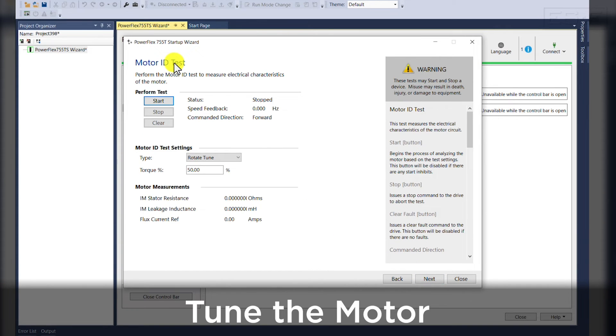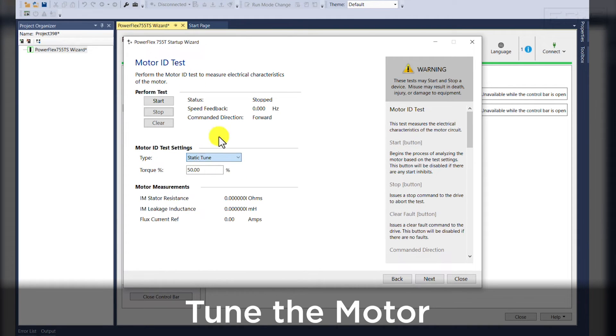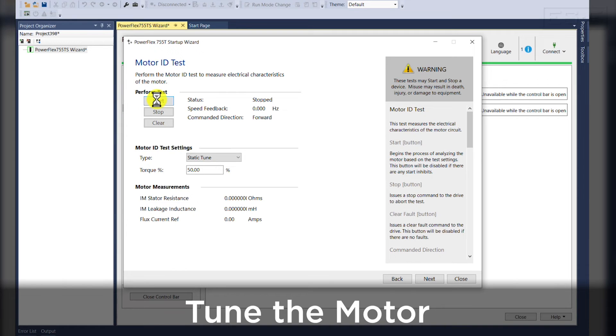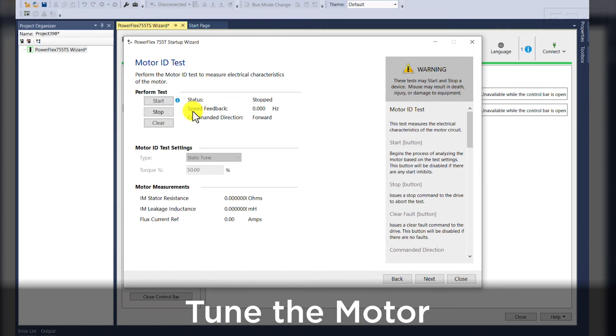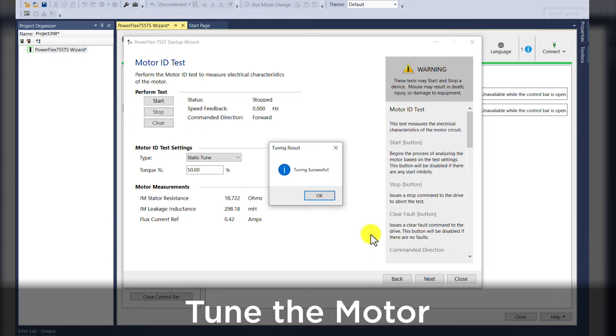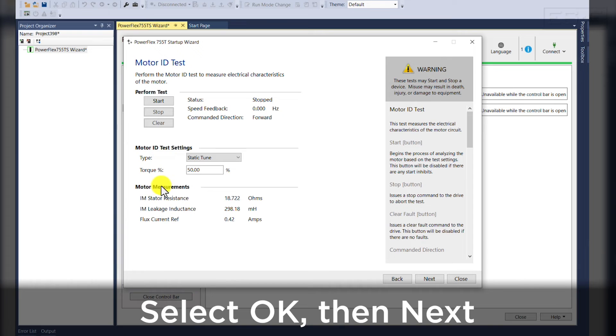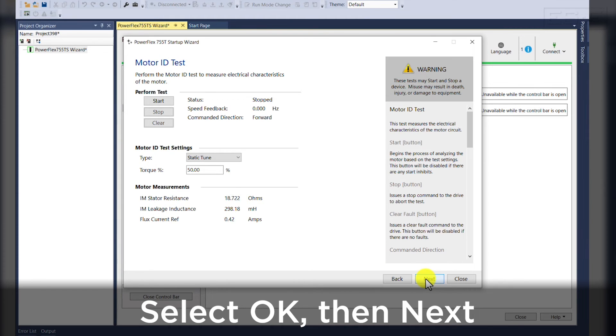For the next portion, we'll do a tuning. In this instance, we'll do a static tune because our motor is coupled with a load. To perform the test, we'll click start and you'll see the status change from stopped to auto tuning. Once the tuning is successful, you'll see down here at the bottom of the screen that your motor measurements have been calculated and these parameters have been changed in your device settings.